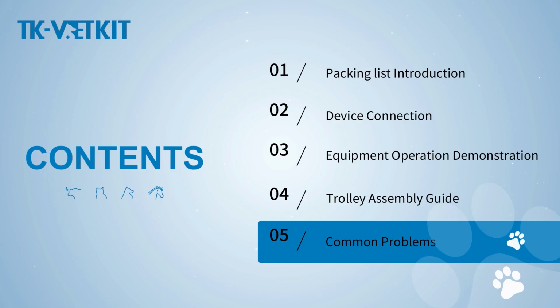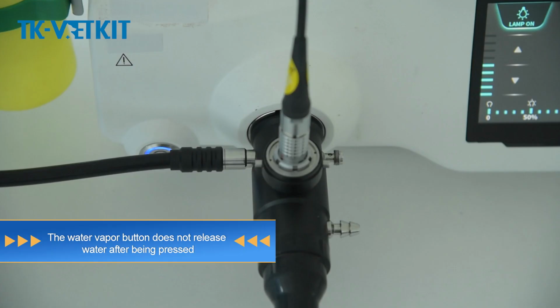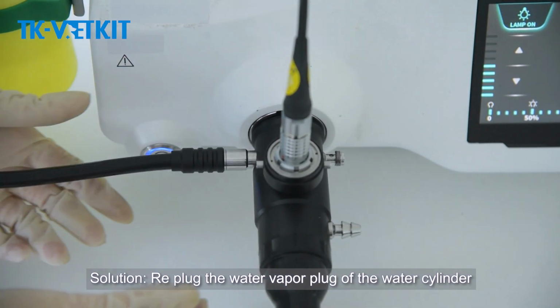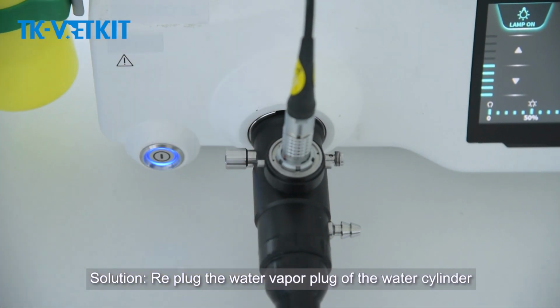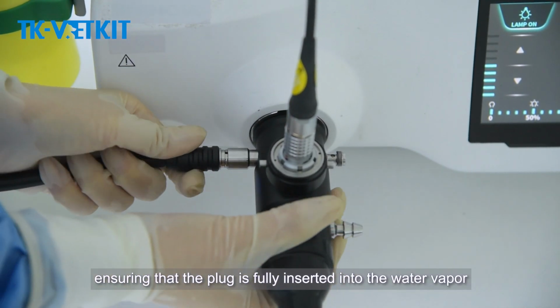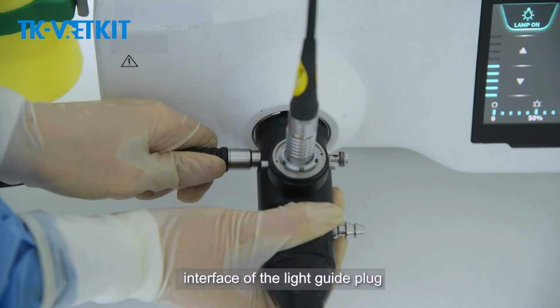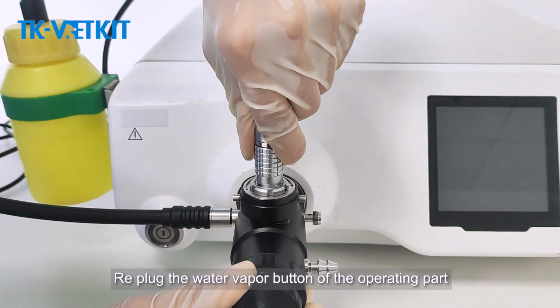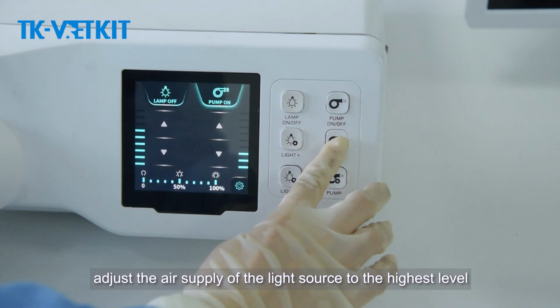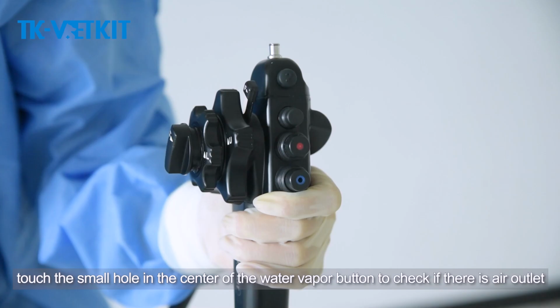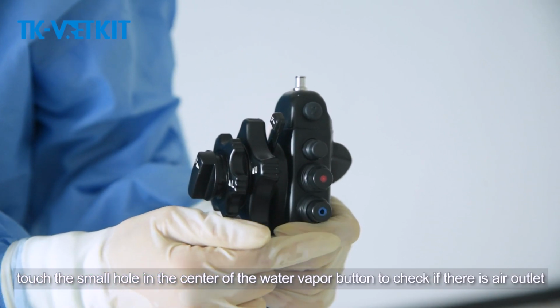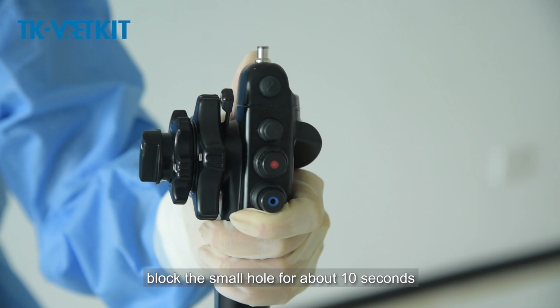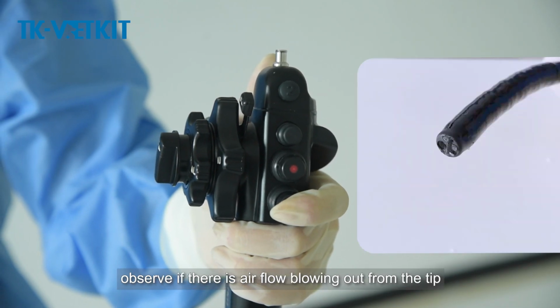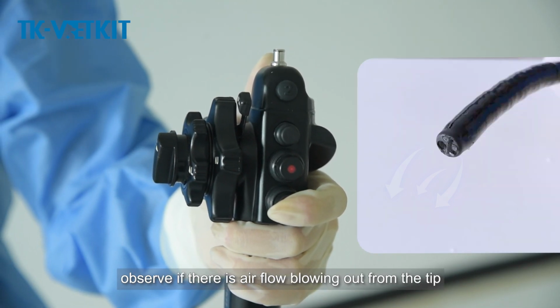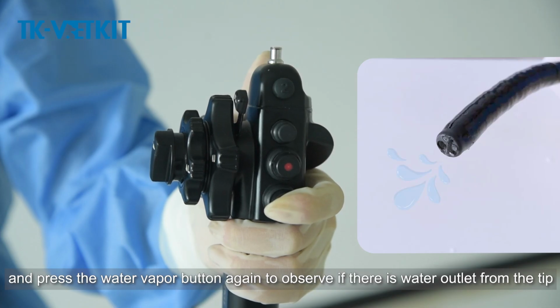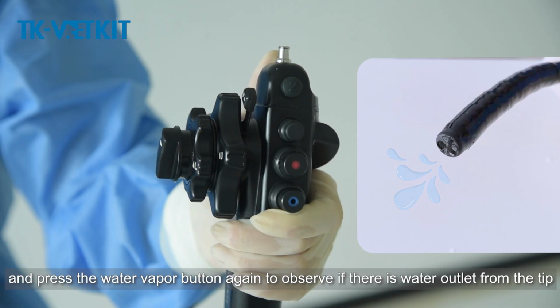Common problems. The water vapor button does not release water after being pressed. Solution: re-plug the water vapor plug of the water cylinder, ensuring that the plug is fully inserted into the water vapor interface of the light guide plug. Re-plug the water vapor button of the operating part, adjust the air supply of the light source to the highest level, touch the small hole in the center of the water vapor button to check if there is air outlet, block the small hole for about 10 seconds, observe if there is air flow blowing out from the tip, and press the water vapor button again to observe if there is water outlet from the tip.